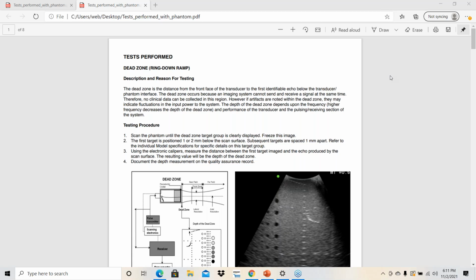It's pretty good. So we have some tests we're going to talk about, and then that's really the end of the lecture. And there's like 8 of them. They're not hard. And I just want you to kind of understand them. They call this dead zone or ring down. And there's a dead zone. You can barely see them. I know the lighting's not good. The presentation is hard to see. When you have it on paper or on your monitor, you'll see it a lot better. But there's a set of dots there, and you're free to look closely, bring the phantom back there. We'll image with it here, but you can see the dots at the top of the phantom.